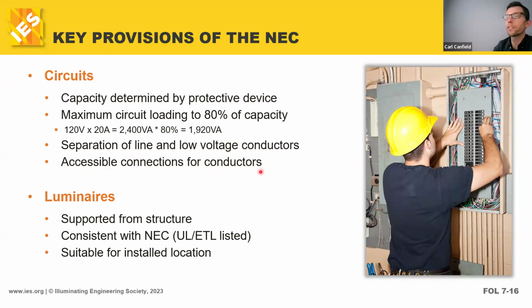Accessible connections for conductors. That just means that in installing a commercial building, we need to have physical, literal access to panels and junction boxes, so that an electrician can come back in and service, repair, and troubleshoot issues in the building after the fact. And so keeping things accessible so we can actually get to them is a big part of the NEC. Requirements on luminaires and lights themselves: they need to be physically supported from the structure. You don't want luminaires dropping on people's heads.